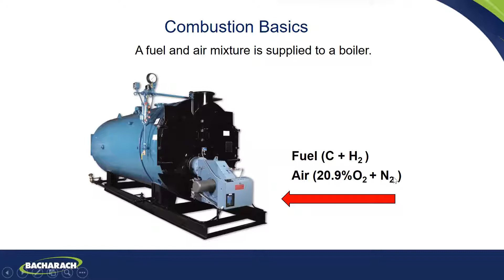Here's our setup—good for any appliance, but we'll use this boiler because I like boilers. We bring in fuel and air and mix it in this power burner, shooting it into what's called a Morrison tube that goes down into the combustion chamber. We have our carbon element and hydrogen element mixing with an oxygen atom, and the rest of room air is basically nitrogen, with maybe 1% other gases as a chemist would argue. So we bring them in here, have a chemical reaction—our combustion—and then those gases go through here.